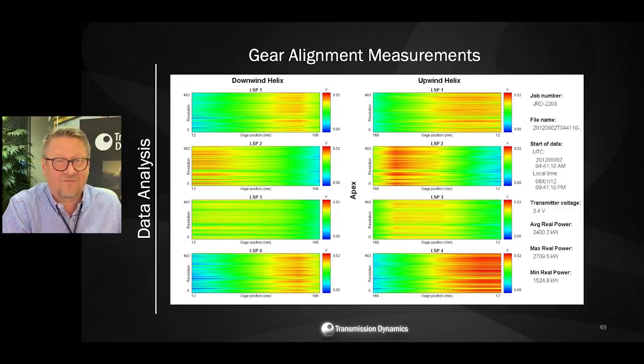But this graph shows it all. This graph here shows the downwind helix and upwind helix of the bull gear engaging with the low speed pinions 1, 2, 3, and 4, driving those 4 generators. And you can also see here that we are plotting load intensity distribution in the form of a Campbell diagram. So the red color is where we have the high intensity, blue is where the intensity across the face width is lower. Also here, we are plotting something like 463 revolutions of the bull gear, which takes approximately 30 seconds, sorry, half an hour.